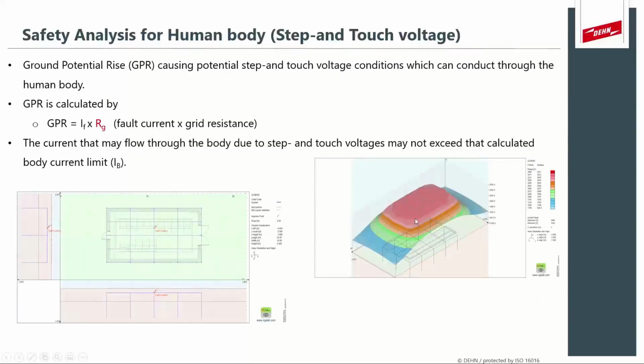So the ground potential rise, as we mentioned earlier, is when a fault gets injected into the earthing system or ground level, and it actually creates this potential gradient, as you can see on the right here, around this grid. This grid is a top view around the building, and you can see the ground potential rise. Now, this ground potential rise, as we said, causes step and touch voltage hazards. The ground potential rise is calculated in a basic or simplified manner, like Ohm's law, where the ground potential rise in volts is the fault current magnitude multiplied by the grid resistance. The grid resistance is highlighted in red in this case because it is dependent on a lot of different factors, like the shape of the earth grid, the soil conditions in the soil model, and so on, which we will discuss next as well.